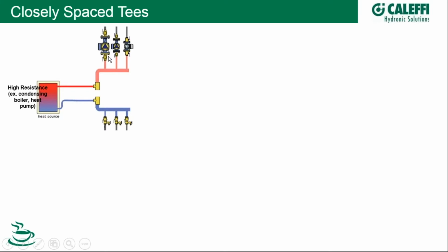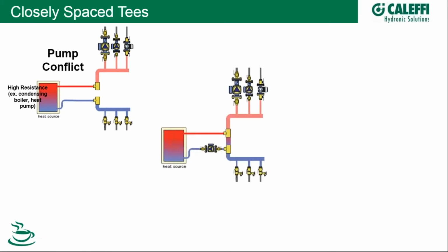So whereby when this pump was off, these were generating 5 gallons per minute and things were happy. Now we might be at 4 gallons or 3, or even suppressing flow almost entirely. So we have a coupled system. So what we want to do now is create a primary secondary arrangement, where we make a connection between these two T's and add a primary circulator.